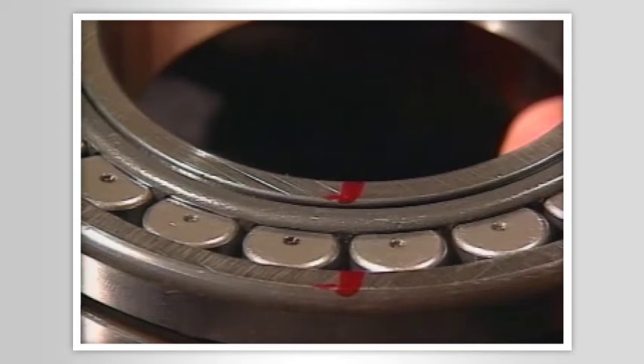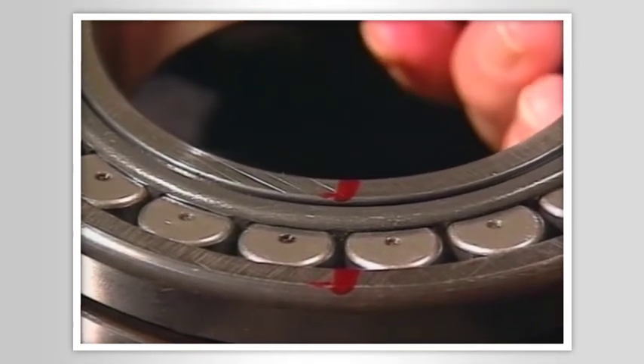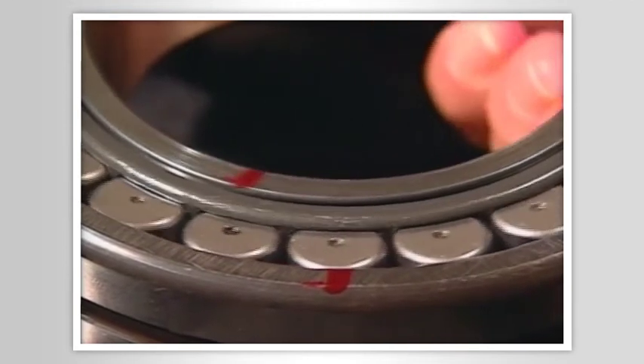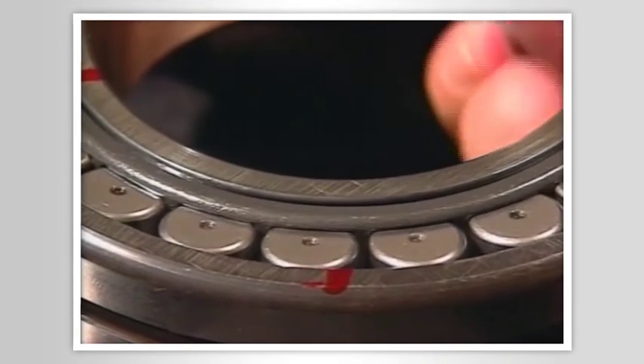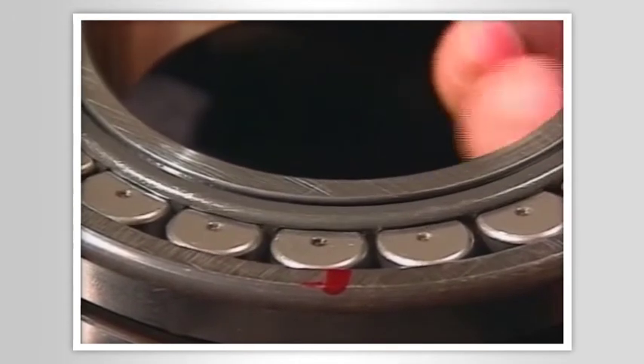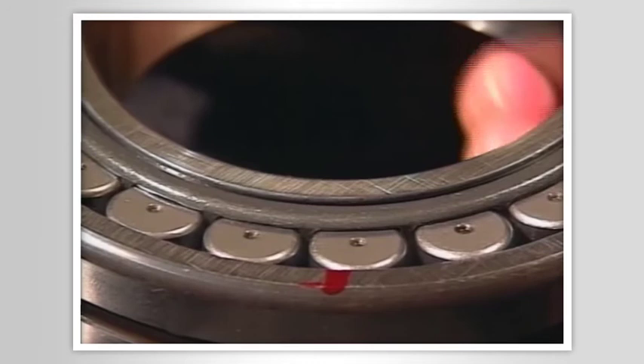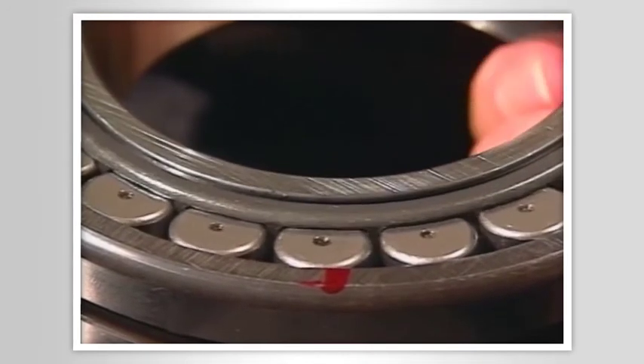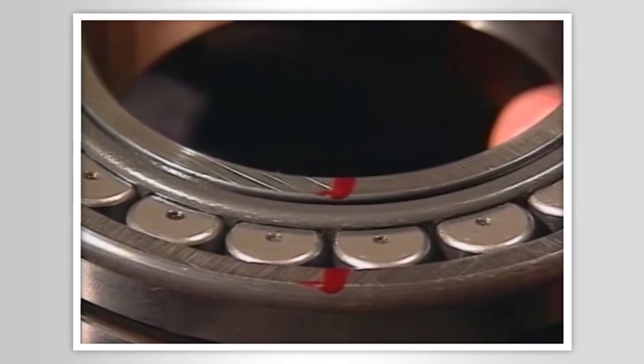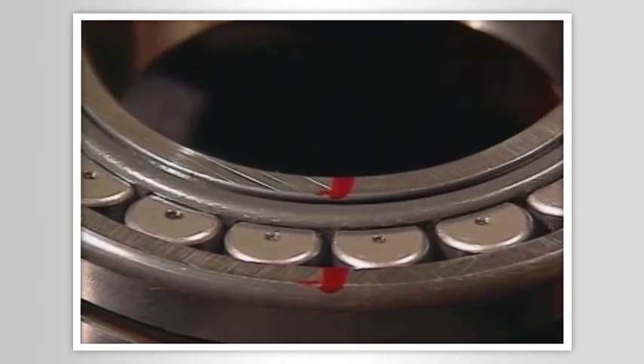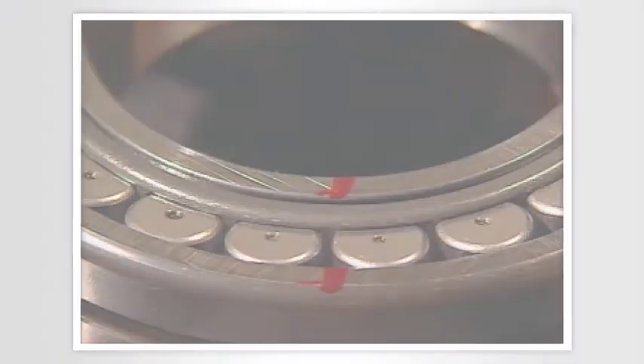Now let's look at the mark on the outer race and count the number of rolling elements that will pass across it in one rotation. 1, 2, 3, 4, 5, 6, 7, 8, 9, and maybe a little more. Looking at the manufacturer's literature, we find a ball pass frequency outer race of 9.02. If there is a defect in the outer race, 9.02 rolling elements will cross it with every rotation of the shaft. So an outer race vibration will be generated at a frequency equal to 9.02 times the turning speed.